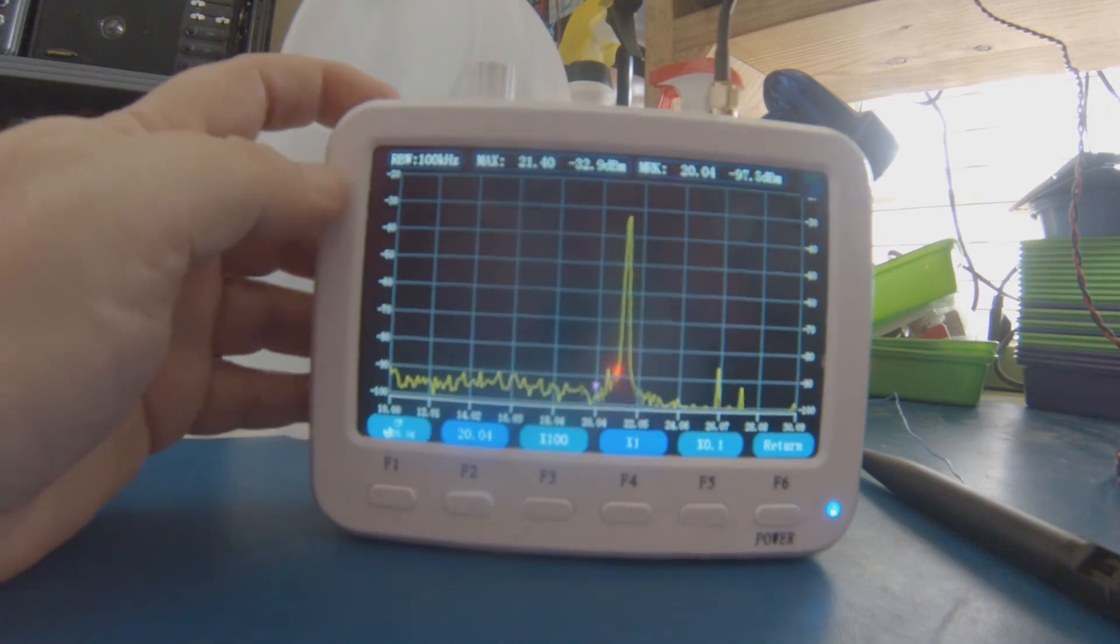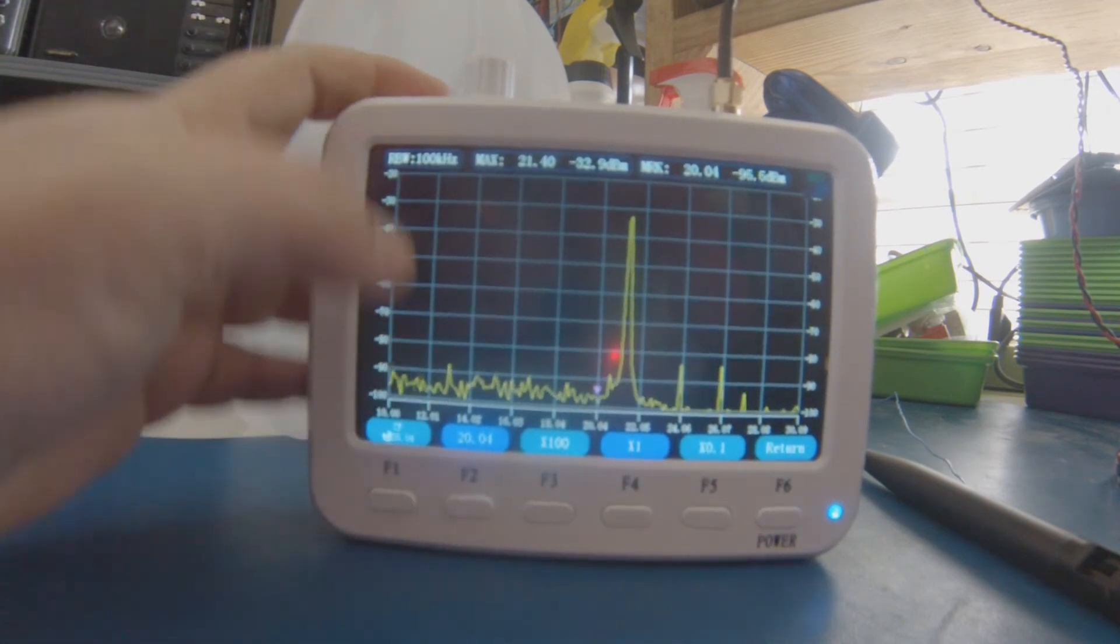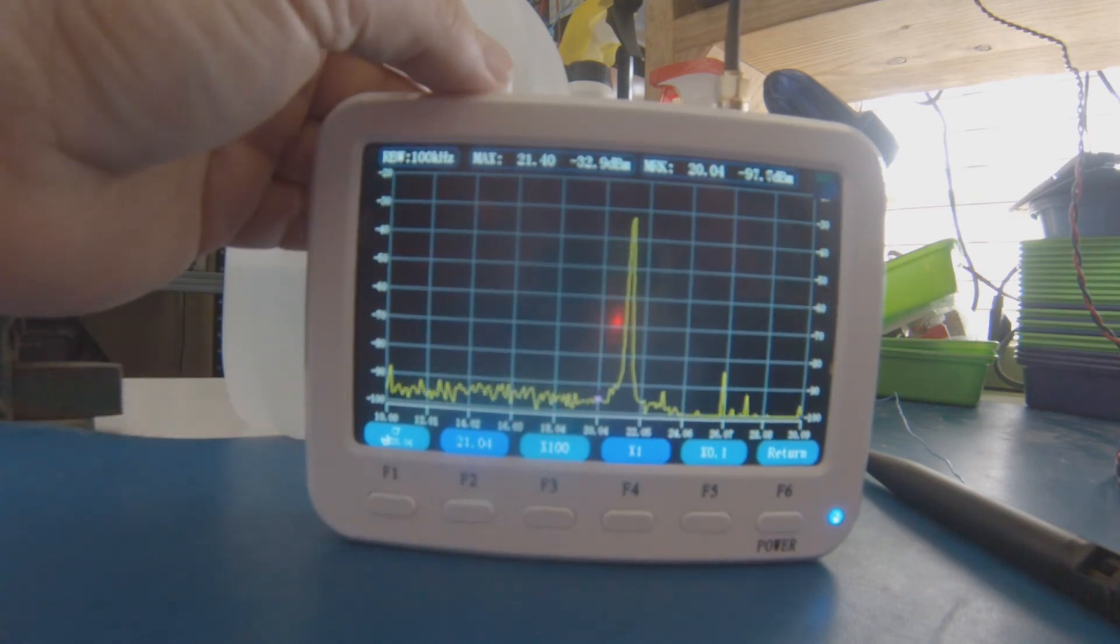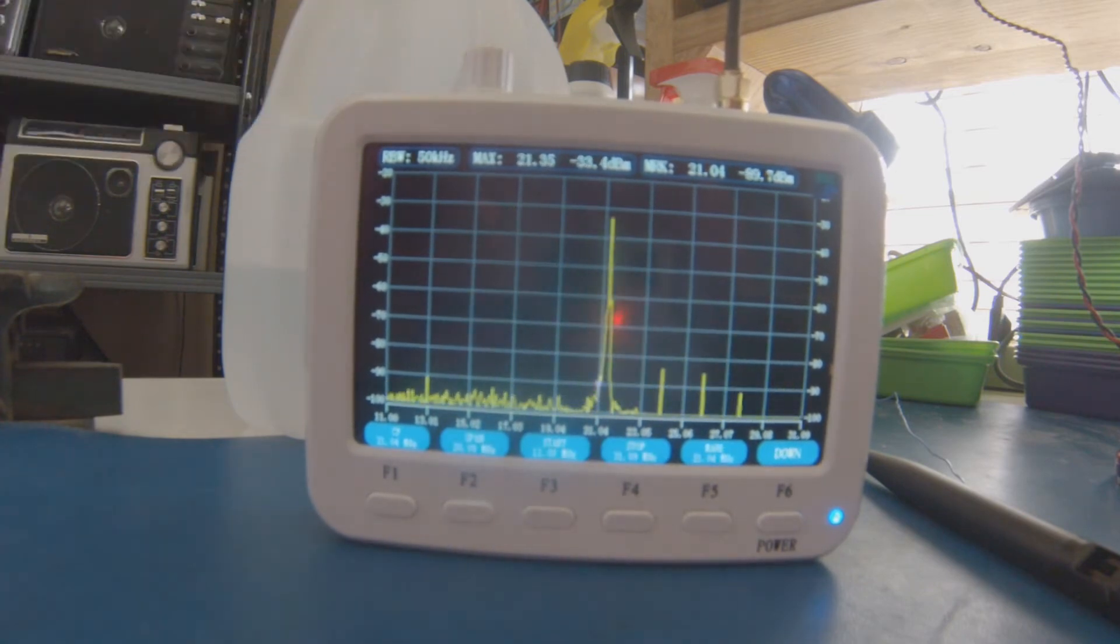So let me set the center frequency here to 21 since that's closer to my peak. I turn the scroll wheel to change it to 21, then push the scroll wheel to perform the action. There you see that my peak is shifted towards the center frequency, which is 21.04.